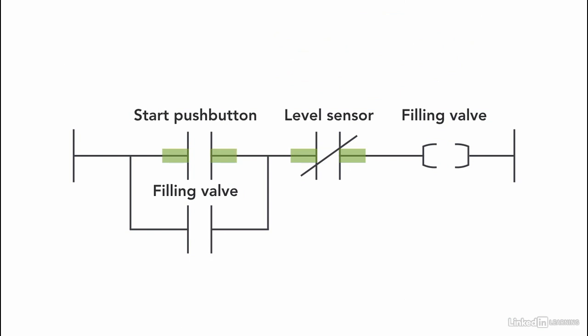Now the program works this way. Once the start pushbutton is pressed, the start pushbutton instruction is activated. And the level sensor instruction is already highlighted because it's an XIO instruction. So the valve opens and stays on. As soon as the liquid reaches the required level, the level sensor will turn on. And the XIO instruction will not be highlighted anymore, and the valve will close.